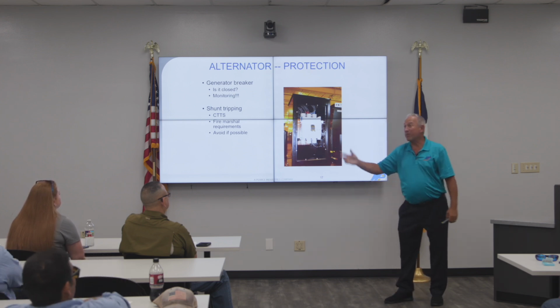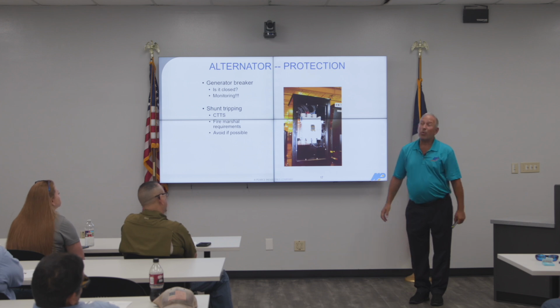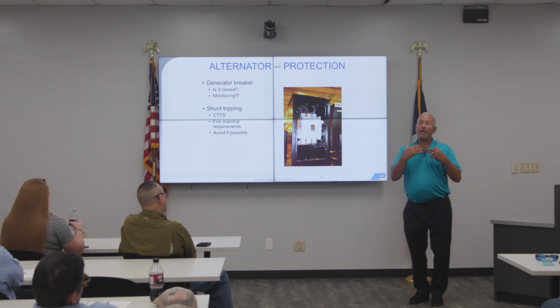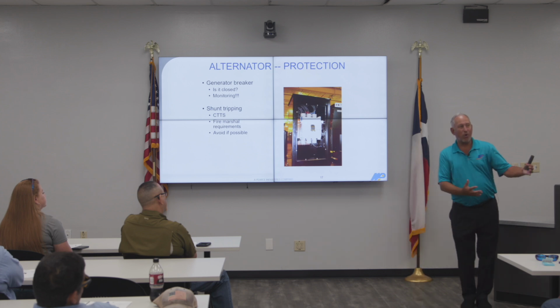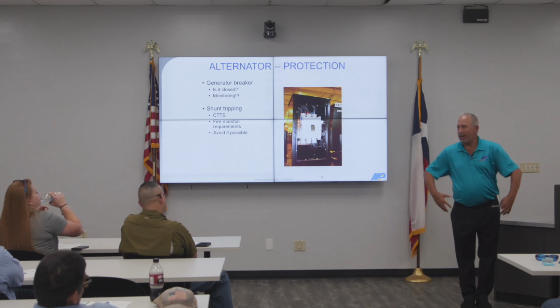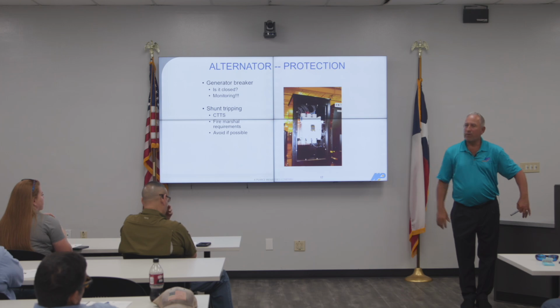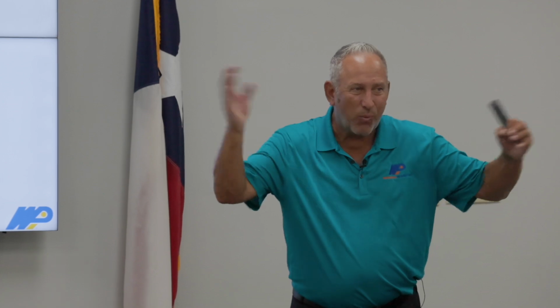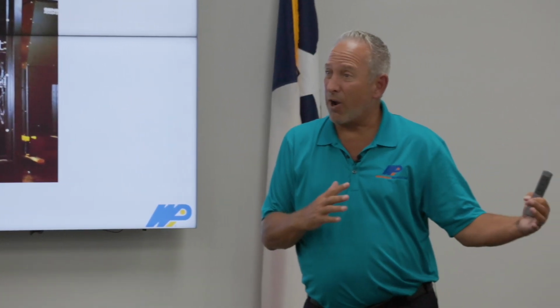But they would watch for storms. If a storm was coming their way, they would make the decision to go onto generators. So by making that decision, you've walked your load over with no interruption at all. And now you just hunker down and let the storm go past you. Because that's generally when things start breaking, right? The utility starts getting weird, different voltages are happening, it's single phasing, whatever, and it could just come in and punch your facility right in the face. So this way they just stay off of it, let it ride out, and then come back.